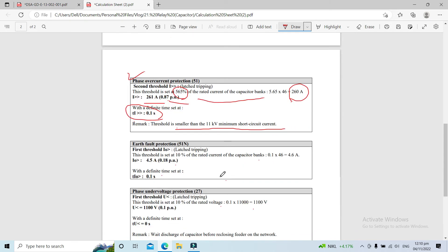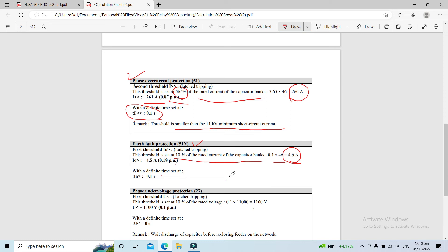Next, for the ANSI 51N earth fault protection, the threshold is set at 10% of the rated current of the capacitor bank: 0.1 times 46 equals 4.6 ampere. We assign the pickup current at 4.5 ampere, which is 0.18 per unit — derived by multiplying 4.5 by the zero-sequence CT ratio of 1/25. The time is set as definite time at 0.1 second.